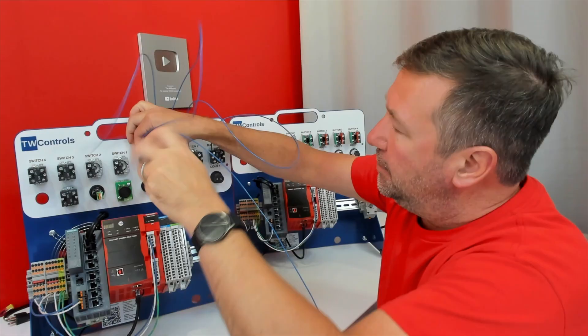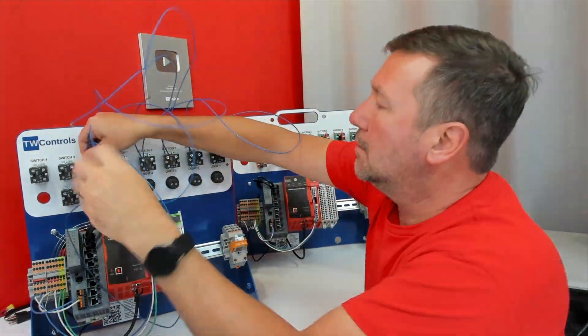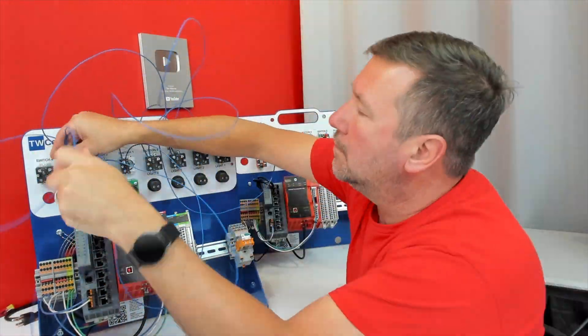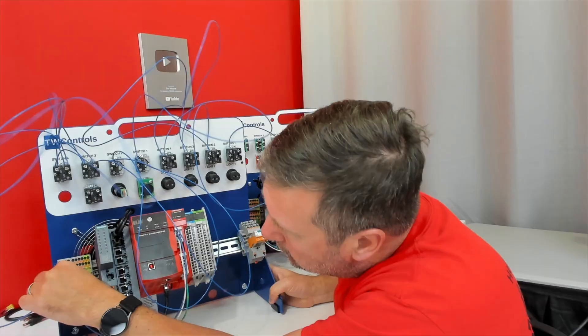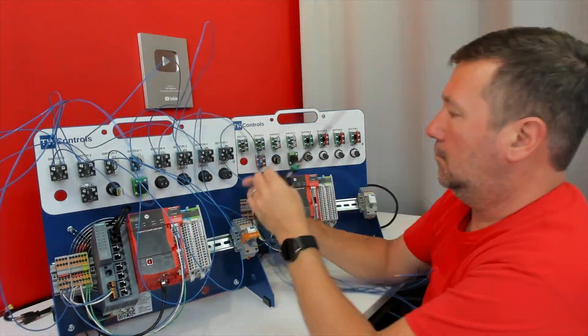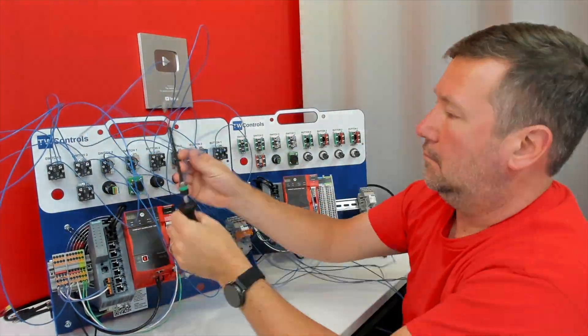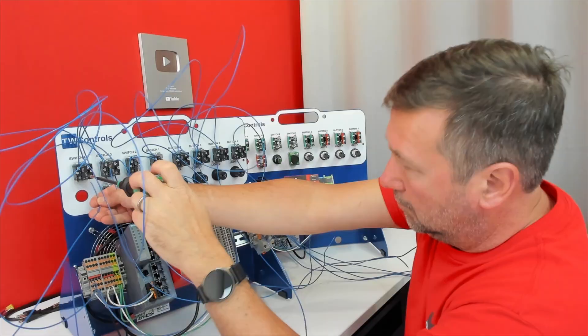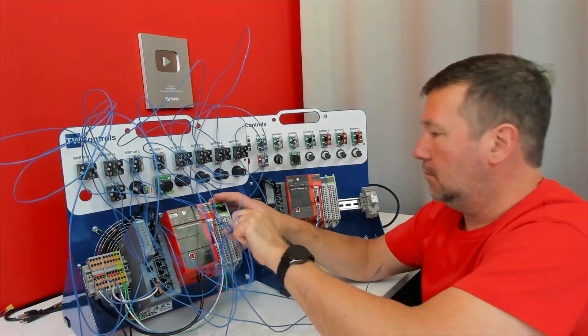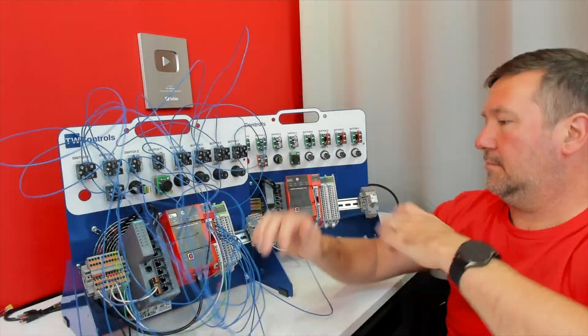Now, a lot of you are probably thinking, couldn't you just use a screw gun and do this faster? Screw guns are not an approved UL device. So we could use them to get us close, but you still have to take your manual torque screwdriver on every single one of them and torque it.